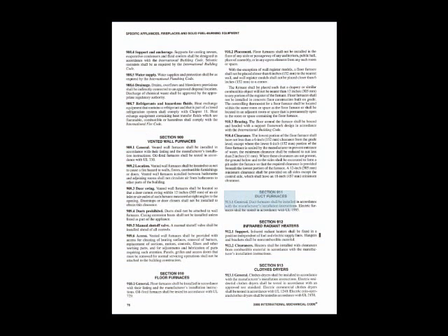911 talks about duct furnaces. Again, UL listed. These are furnaces that are inside ductwork. Very specific because of fire issues. Have to have airflow. 912 talks about infrared space heaters and basically says install in accordance with manufacturer directions. 913 talks about clothes dryers. They have to be UL listed. 914 talks about sauna heaters, the guards, what type of warning notices are required for people using a sauna.